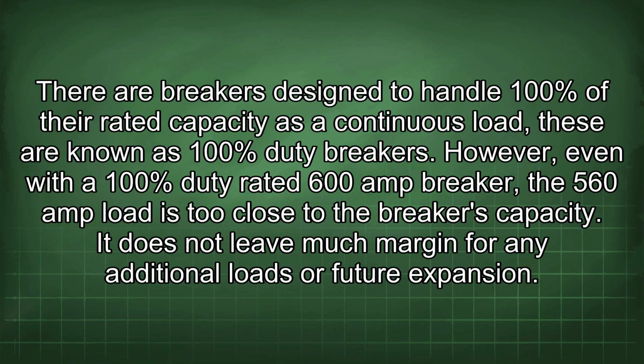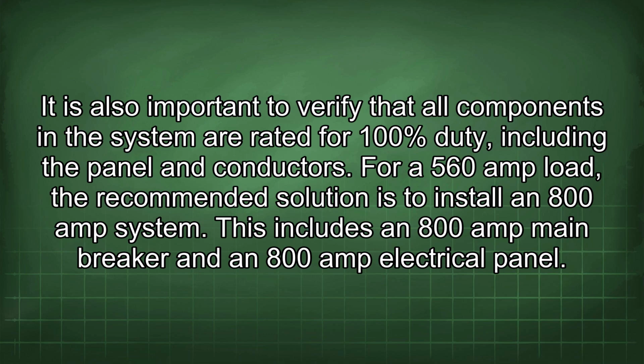There are breakers designed to handle 100% of their rated capacity as a continuous load. These are known as 100% duty breakers. However, even with a 100% duty rated 600 amp breaker, the 560 amp load is too close to the breaker's capacity. It does not leave much margin for any additional loads or future expansion. It is also important to verify that all components in the system are rated for 100% duty, including the panel and conductors. For a 560 amp load, the recommended solution is to install an 800 amp system.